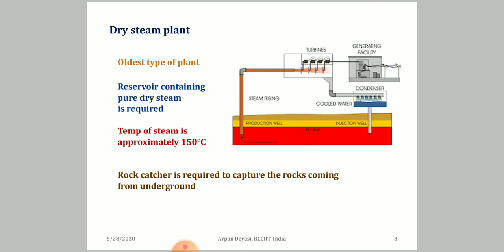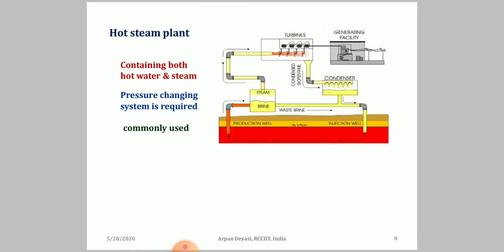The dry steam plant is the oldest type of plant. The reservoir contains pure dry steam, with temperature varying from 150°C to 200°C. Rock catchers are required because heating can dislodge rocks, which can damage mechanical infrastructure such as the condensation system, turbine, or electricity generation equipment. So rock catchers are essential for dry steam plants.